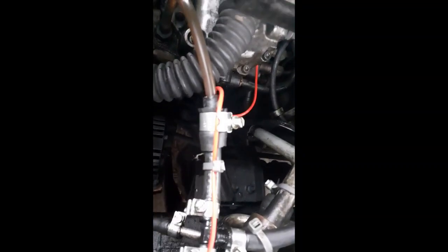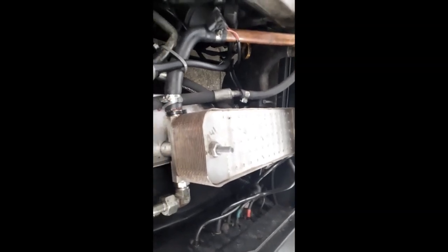So the looped return sends the return back from the pump, back to the feed line into the pump - it's got a loop. The benefit of this is that it reduces how much fuel is coming up the feed line. It can spend a lot longer in your heat exchanger warming up, because the flow through there is a lot slower, so it can pick up a lot more heat.